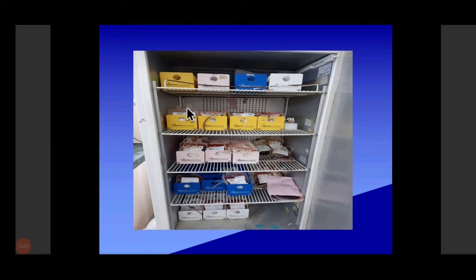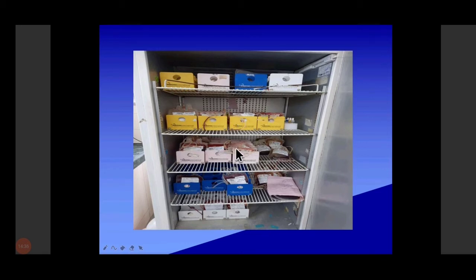The difference between a normal fridge and a blood bank fridge is that there is no freezer compartment and no stands inside the door. Blood bags are properly arranged by blood group — they should be separated. Orders should be separated by blood group columns: A, B, AB. No food should be kept here. The blood bag should always be kept in the upright position, not on a slant.